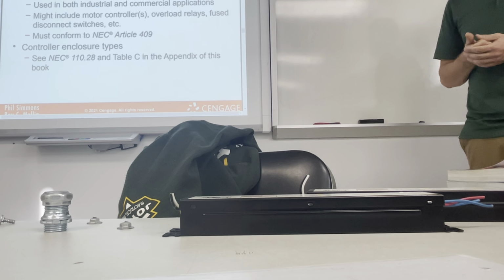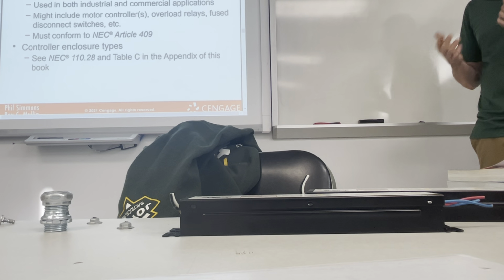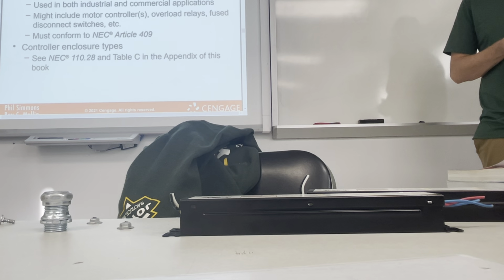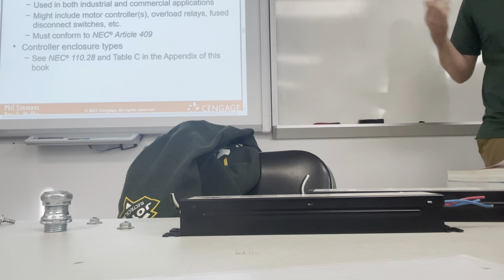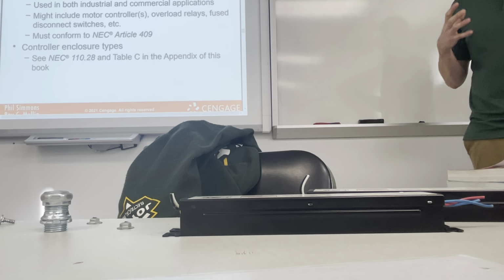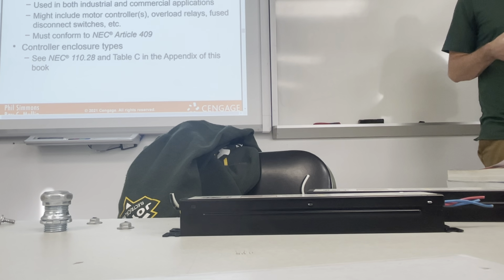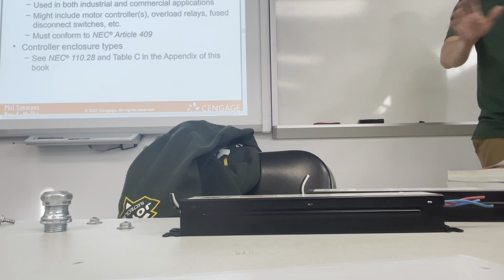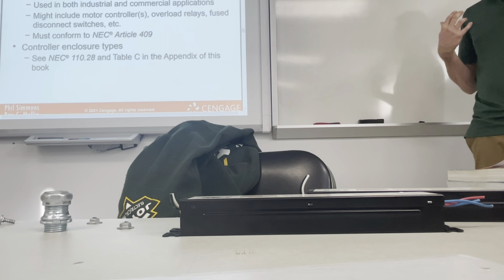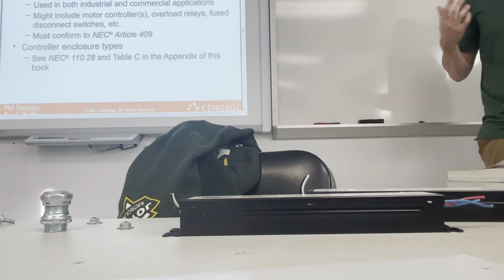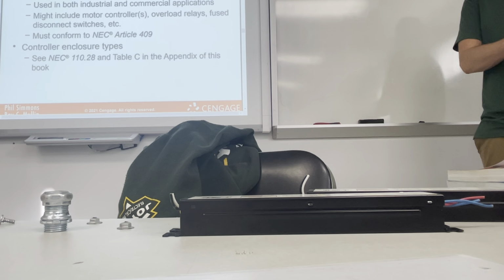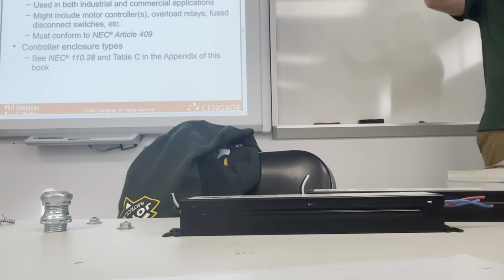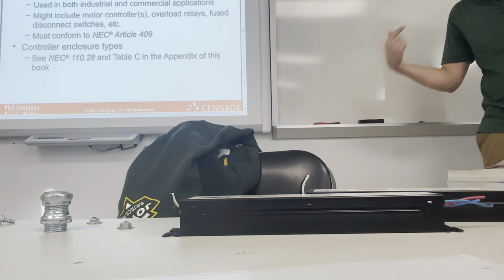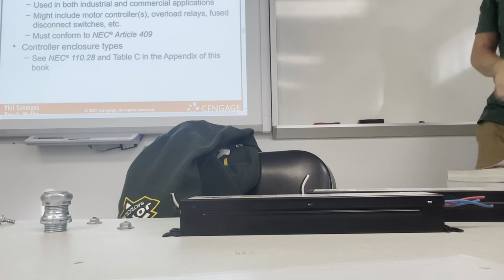And two, if there's ever a short circuit problem, a three-phase, leg-to-leg issue causing an arc flash and arc blast, you would rather that be nice, burly, and self-contained, right? If that blows up, you don't want that lid flying open and spewing all that molten copper at you, do you? No, so they're usually rated to carry that kind of condition, and they're usually isolated or self-contained. So if one were to blow, it's not going to cause a chain reaction of everything blowing around it.